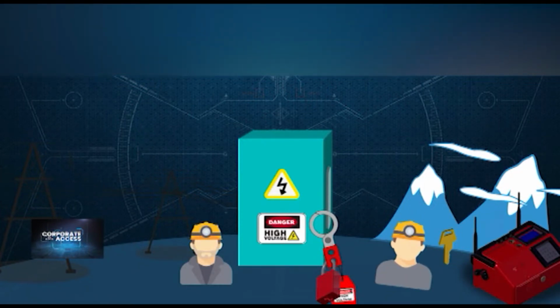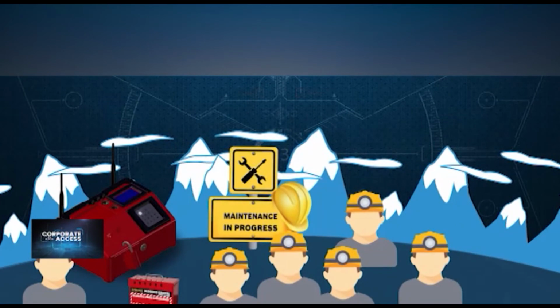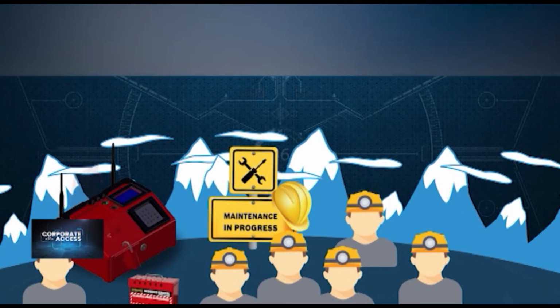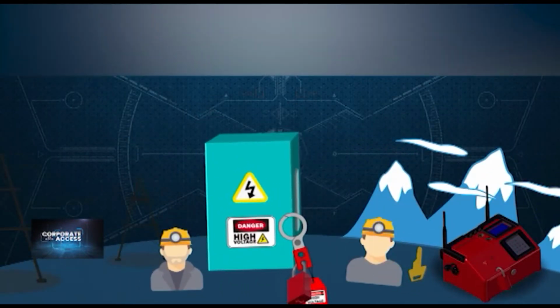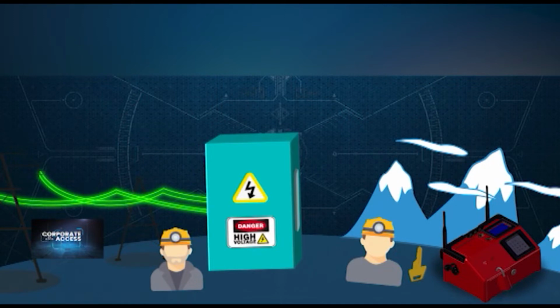that physical key. So in other words, we place one device in the substation and another device on the asset to perform the maintenance. The same key from the isolation panel goes to this device on the substation, and after the safety procedures, the device on the field, on this asset, will release a key from inside of this device. So we joke that we teleport the key, but of course we have two different keys under the same state machine. And when the crew on the maintenance side see the physical key getting out of this box, this is the physical proof that the isolation has been performed on the other side.